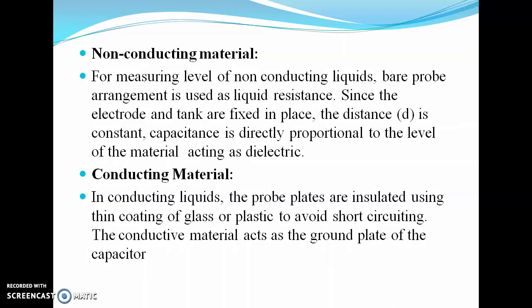In the case of conducting material, in conducting liquids the probe plates are insulated using a thin coating of glass or plastic to avoid short circuiting. We have to take care that there is no short circuit, as the material inside the tank is conductive. The conductive material acts as the ground plate of the capacitor.